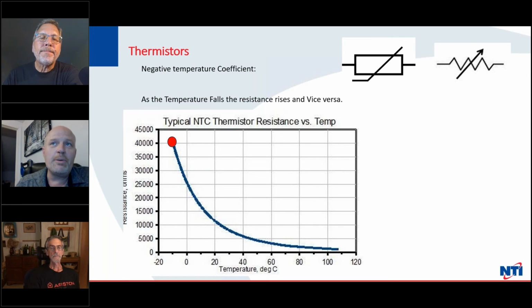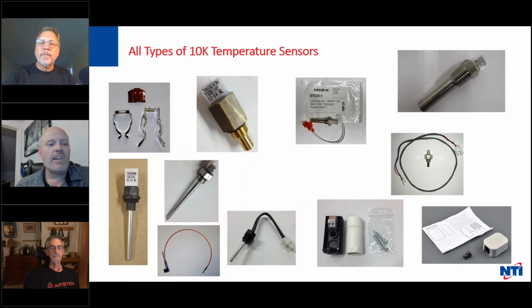Most of you will touch a pipe and, within 10 or 15 degrees, you can probably tell me how hot it is. If you've got a bad sensor, it's usually so far off that you can touch the pipe and the boiler says it's 200. Well, we know that's probably wrong. So trust your hands and look at the readings that you see on the screen.